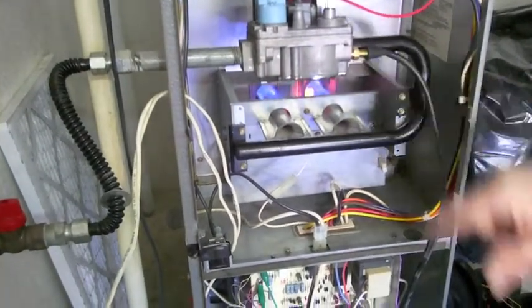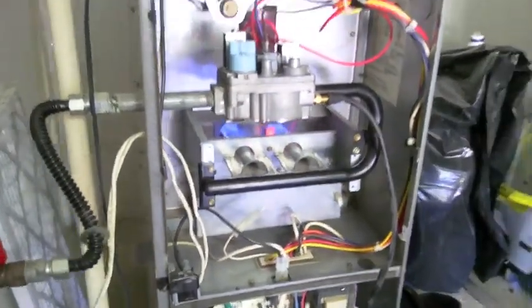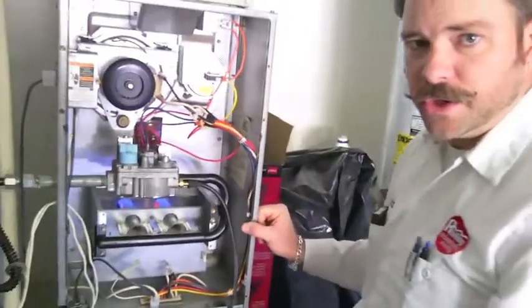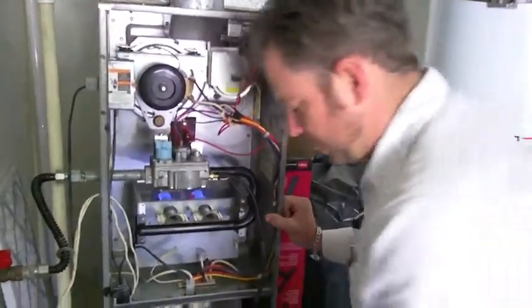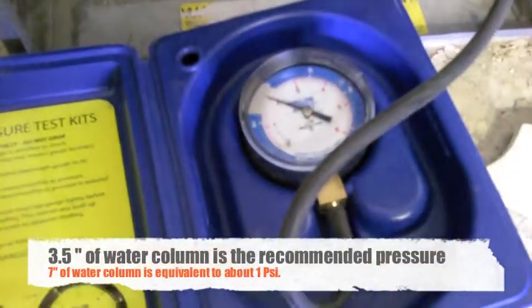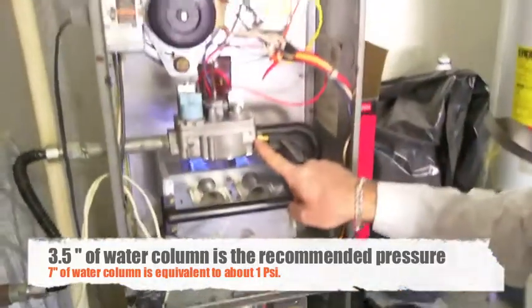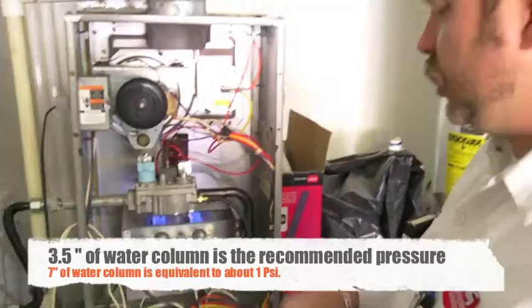We're looking for a nice blue flame. We don't want to see very much, if any, orange flame. It should all be blue. And if you look right here on the gauge, this is right about 3.5, so that's good gas pressure. We want to leave this hooked up because if we unhook this right now, we'll get gas shooting out.